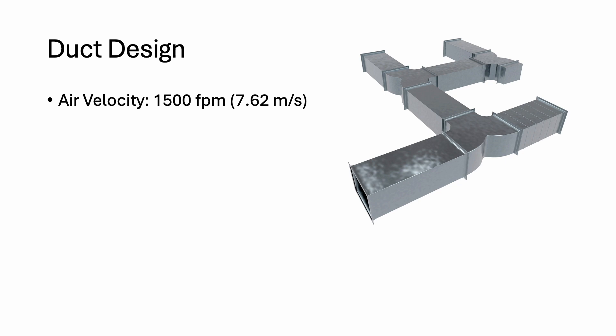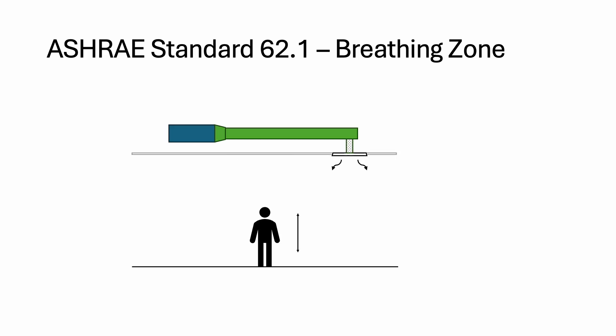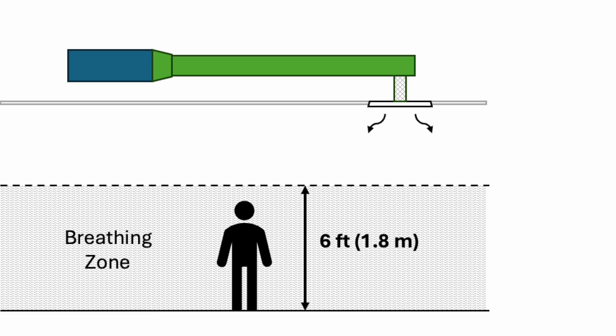According to ASHRAE standard 62.1, 6 feet or 1.8 meters from the floor is defined as the breathing zone. To ensure occupant comfort, the supply airflow must be at a velocity between 50 and 100 feet per minute before entering the breathing zone.